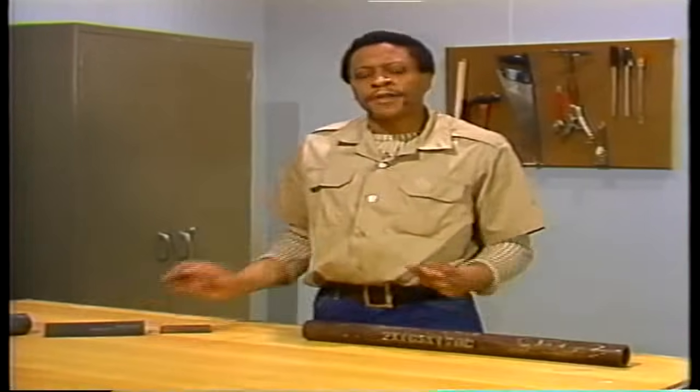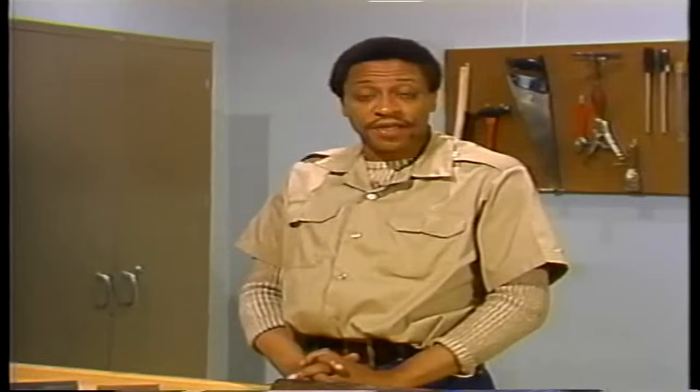Vibration sets up another kind of mechanical stress. The flow of water or steam through a tube and the flow of hot gases around a tube can sometimes cause vibration. As a tube vibrates, it bends back and forth over and over again. This repeated bending can cause the tube metal to crack — this is called metal fatigue.